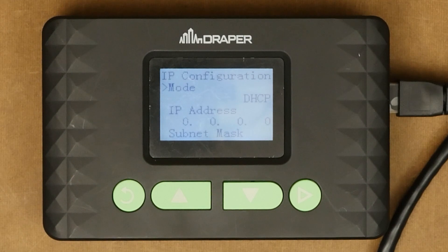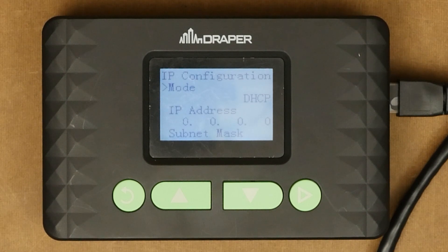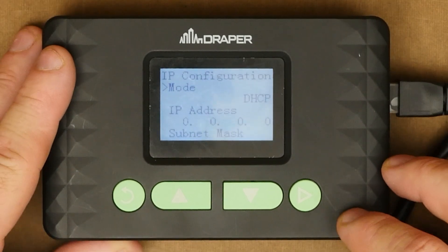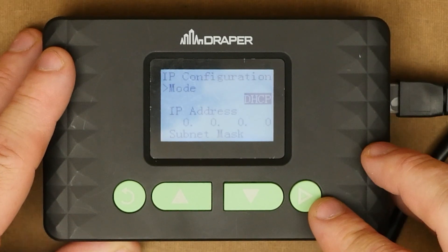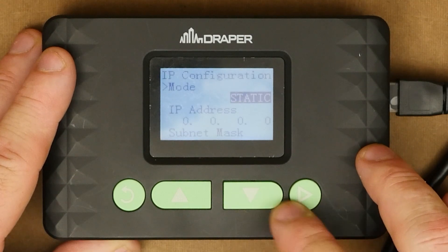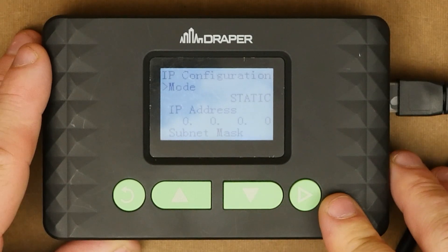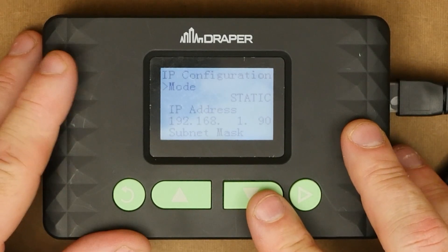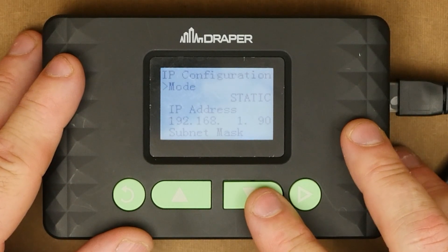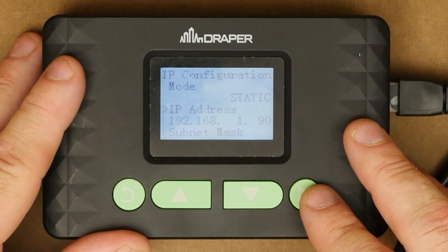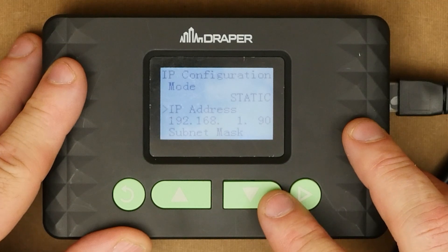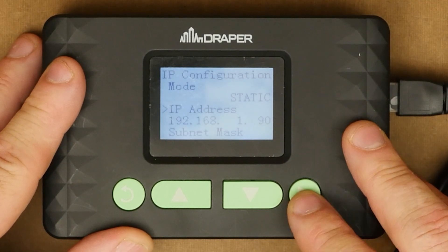By default every IP gateway ships out under DHCP, meaning it's going to obtain its IP configuration from the network it's plugged into. However, if they have specific IP information or if you're setting up a dark network, we're going to want to change this to static. To do so, select mode and hit enter. DHCP will highlight — use your up or down arrows to navigate to static and then hit enter again. We now have a static IP and it automatically defaults some IP information in there, so we're going to go ahead and change that.